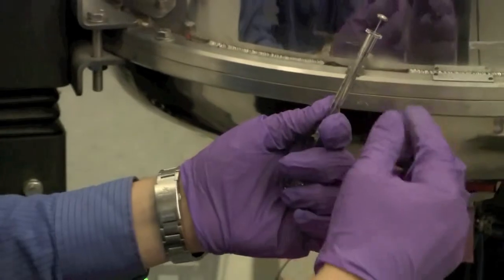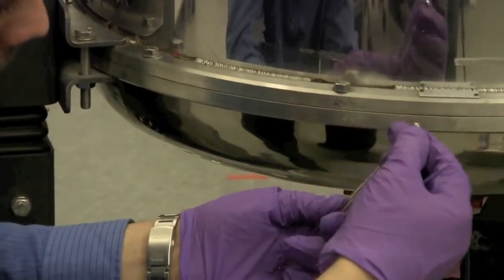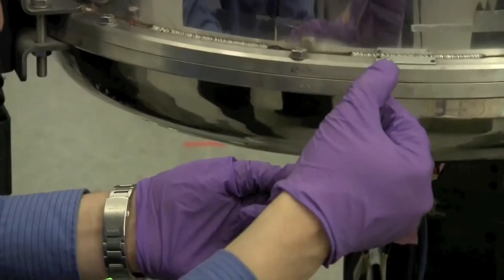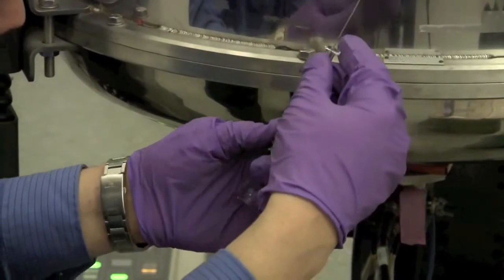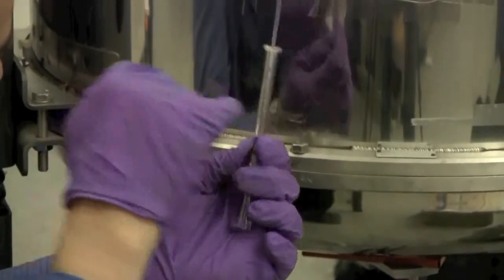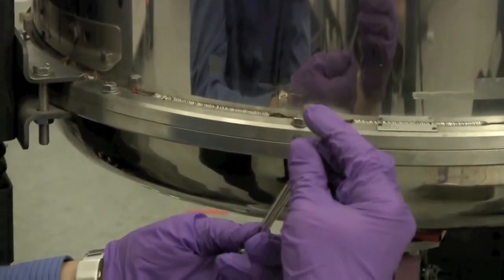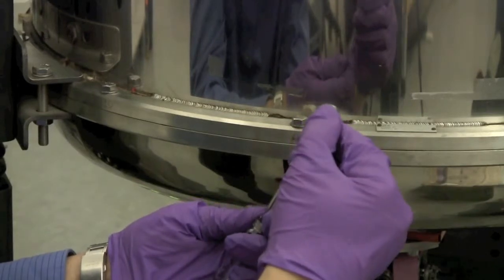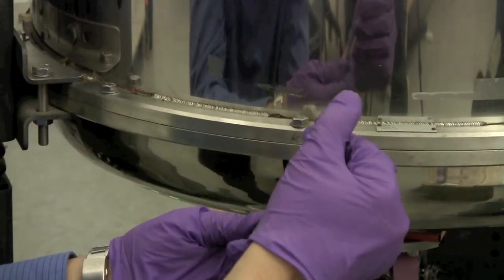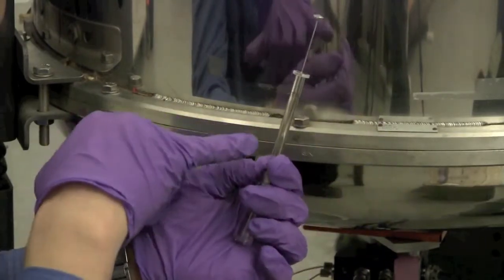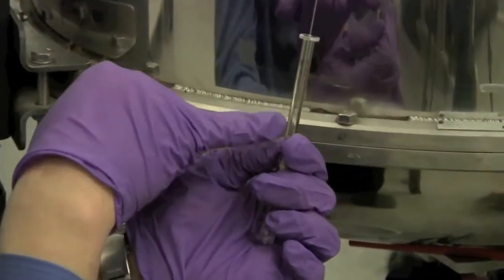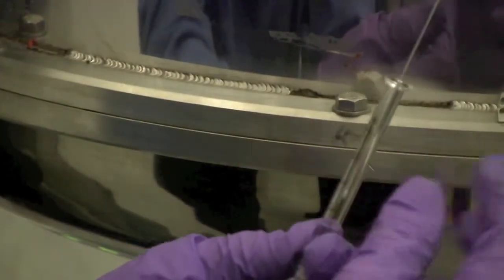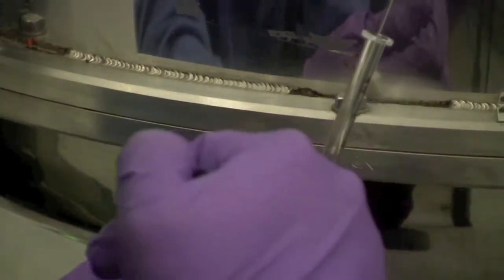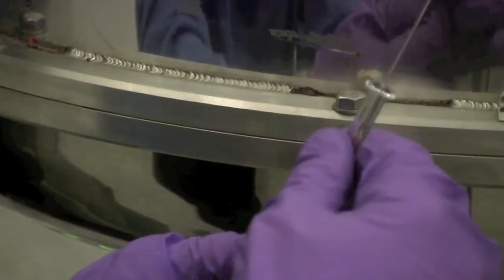If you have an extra sample, you can draw it up, but you need to draw up at least 25 microliters of sample. If you have an air bubble, you need to make sure it's at the top, and if you can, you want to try to get rid of it as much as possible. In the cleaning stage, it wasn't really a problem if there's an air bubble, but in here, if there's a bubble in the middle of your column of sample, that's going to go into the probe and put a bubble into the coil, and that's going to screw up your shimming. So we want to make sure it's free of air bubbles, and again, you want at least 25 microliters of sample.